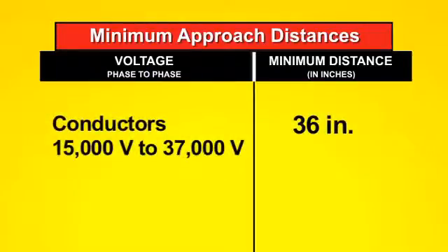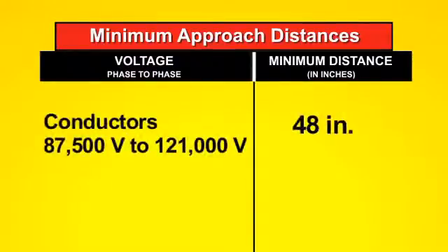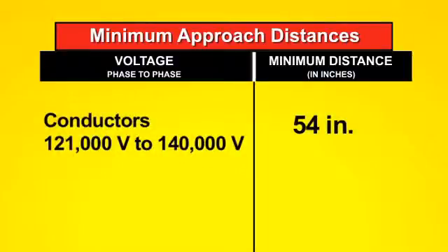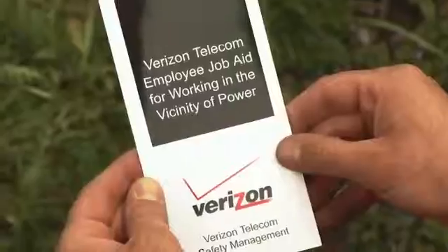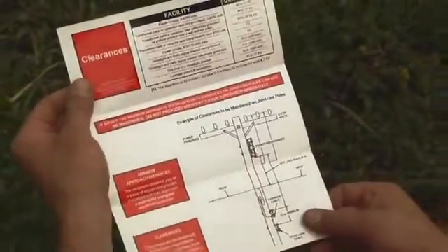For 15,000 volts to 37,000 volts, stay 36 inches away. For 37,000 volts to 87,500 volts, stay 42 inches away. For 87,500 volts to 121,000 volts, stay 48 inches away. And finally, for 121,000 volts to 140,000 volts, maintain 54 inches between you and the energized conductor. If you're not sure what the required clearance or approach distance is, check the Trifold electrical safety handout available in the Verizon ordering catalog. You should always have a copy in your vehicle. If you don't, get one from your supervisor.